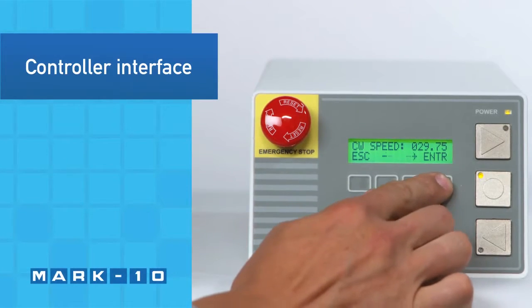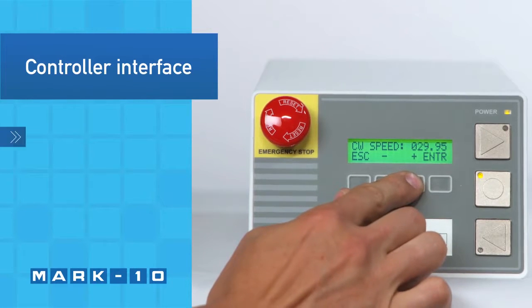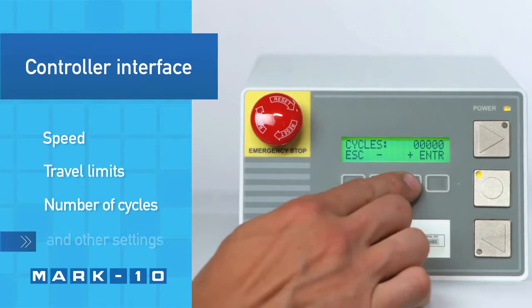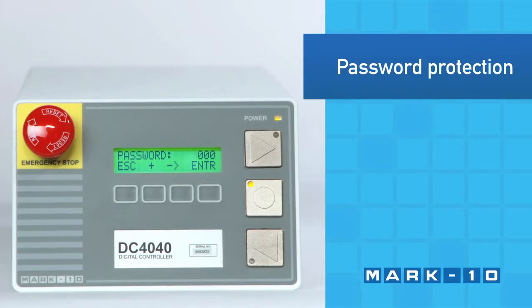Utilizing the simple controller interface, set up test parameters such as speed, angular travel limits, number of cycles, and other settings. Password protect the menu to prevent unauthorized changes.